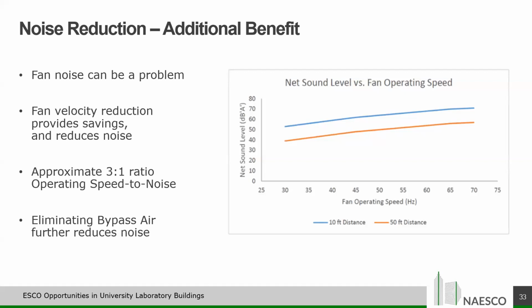Some of these universities are nestled in a residential area and you get noise complaints from the neighbors. I've been on university roofs where they're like, hey, anything you can do about the noise? And this helps. When you reduce that discharge velocity and ramp your fans down, you get significant reduction in noise.